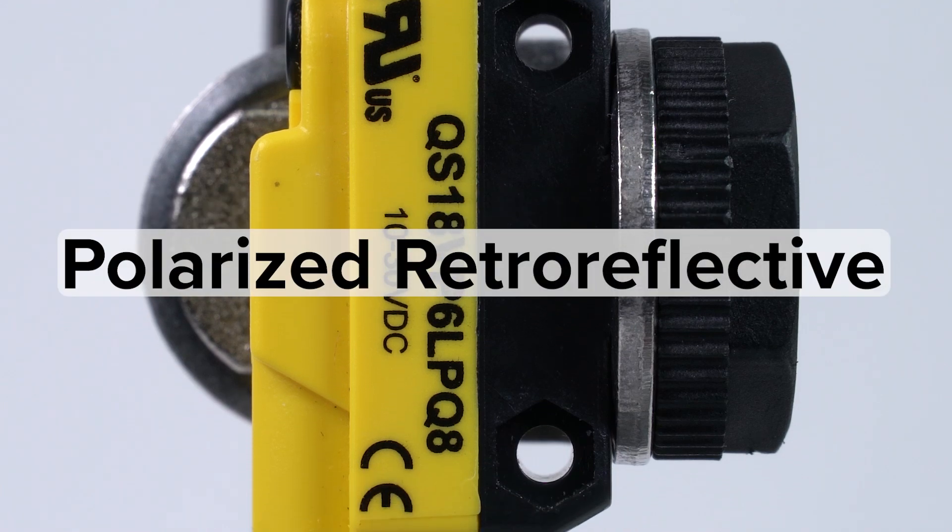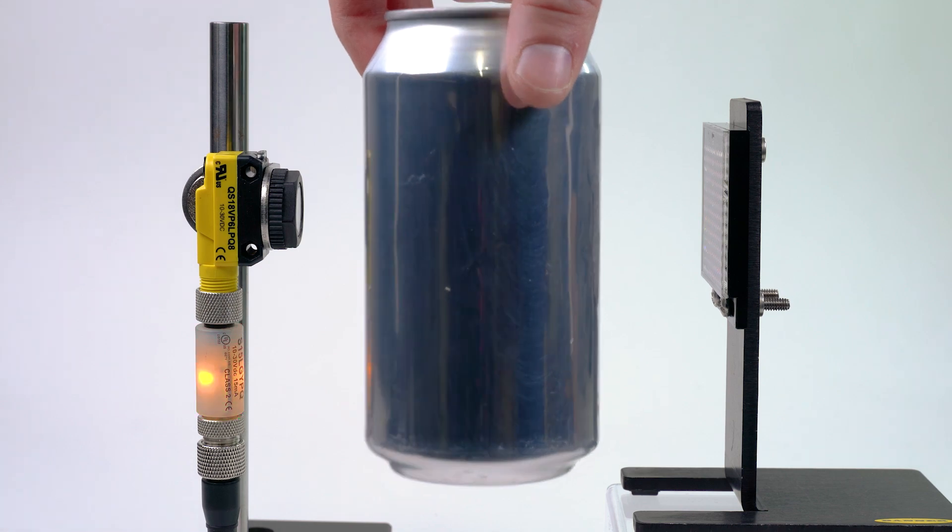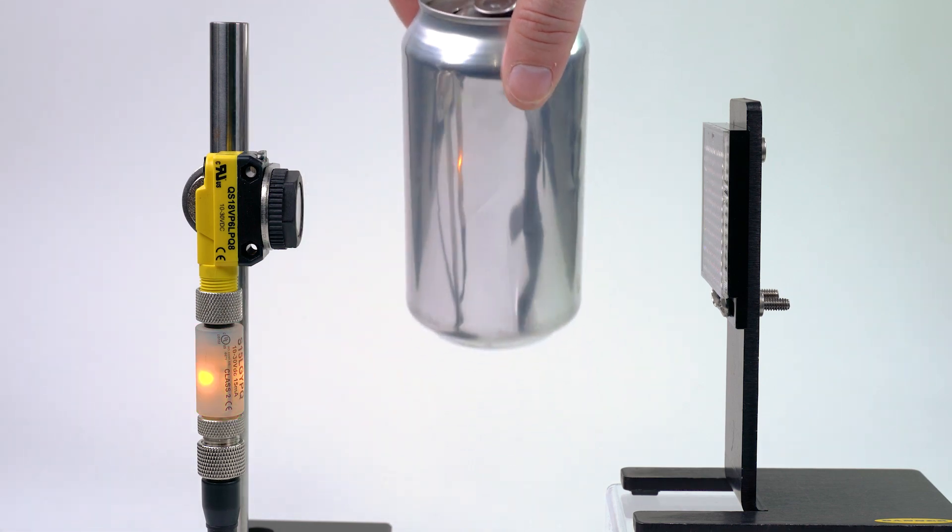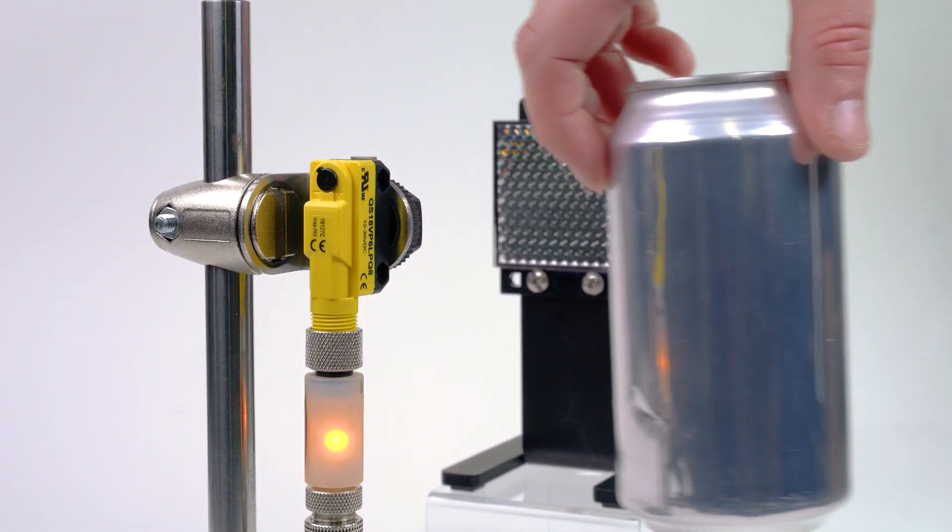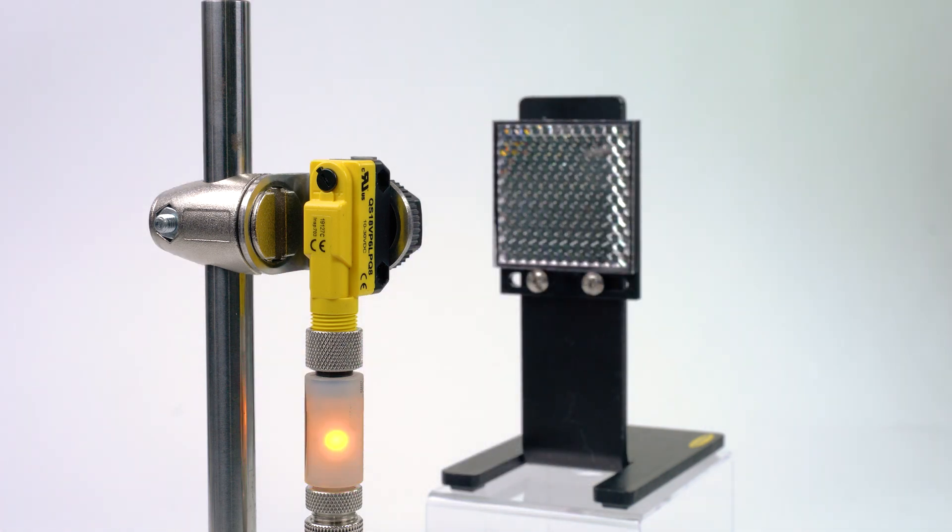Switching to a polarized sensor will help detect even the most reflective of targets due to the polarized filter in the sensor lens. The polarized option is recommended for most retro reflective sensor applications.